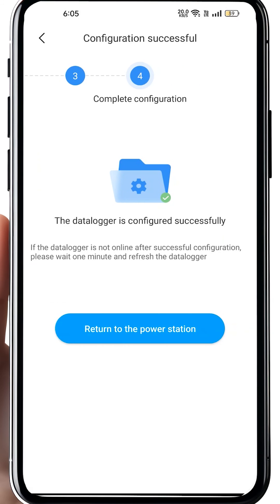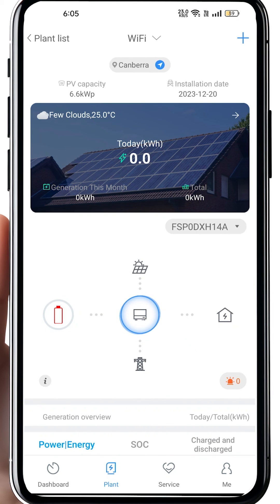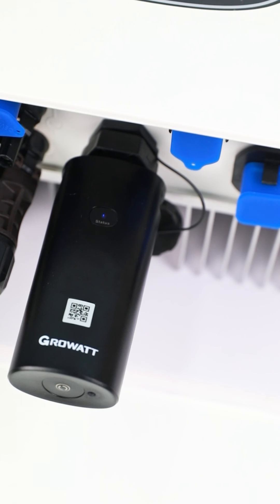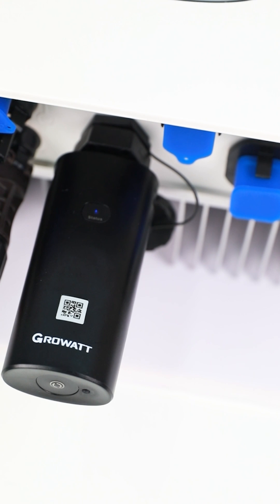It will probably take about 20 to 30 seconds. Once done, it will show that the configuration is successful. Then click 'Return to the Power Station' and do a refresh on this page. You will get all the latest information of this inverter. The blue light on the Wi-Fi dongle means it is working perfectly.